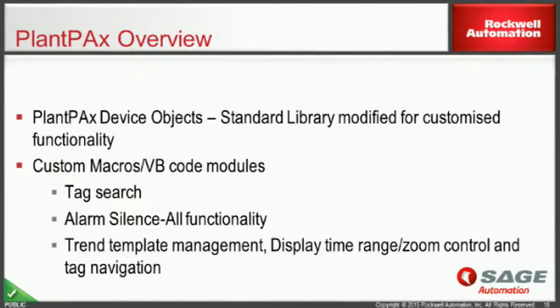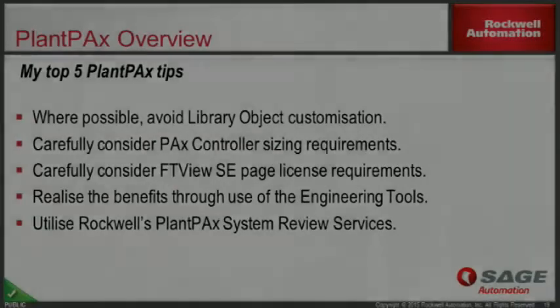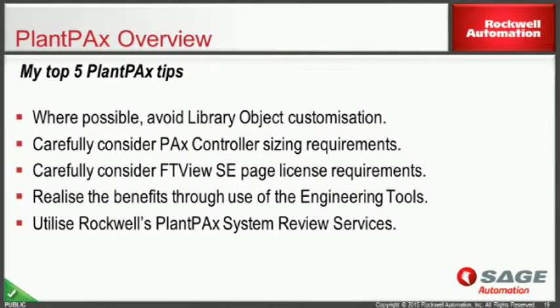We did customise PlantPAx device objects due to specific customer requirements, trying to get that old for new expectations working. And we built custom macros and VB code macro modules for tag search functionality, alarm silence all functionality between different clients within different buildings or the same area, and trend template management, display time range/zoom control, and tag navigation from the trend pages. The top 5 PlantPAx tips.